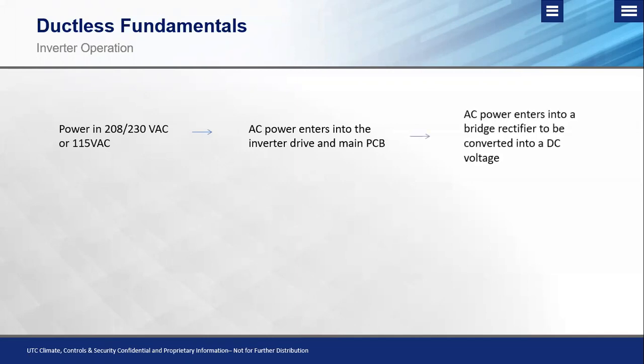Now from there, we take that AC power, we rectify it over into DC, and we send the AC and the DC voltage out to the appropriate places depending on what time of year it is and how the system's running. But as a generic overview, we're going to send that out to different parts of the system. Now, in this case, we're going to carry on and look at the compressor, the actual inverter compressor operation. So that AC power, we now know, enters into the main PC board. That AC power then enters into what we call a bridge rectifier, as I covered earlier, which takes the AC voltage over into DC voltage, or we get that rectification process.